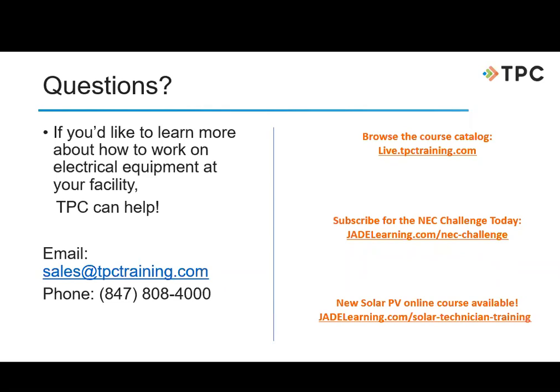Great call. Just a brief topic on the whole idea of troubleshooting in three phase. What can cause one of these three phases to drop out, and what happens when they do? Great question. So, a lot of different reasons that we could go to single phasing. By that we mean, if the utility is giving us all three phases, and then we start to single phase, it means we lost a phase somewhere.